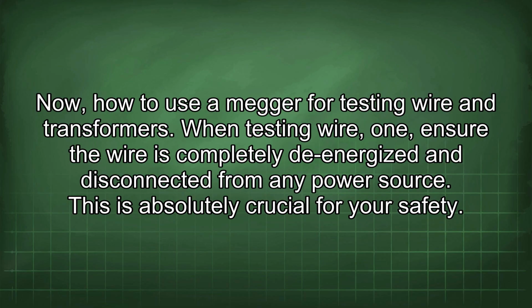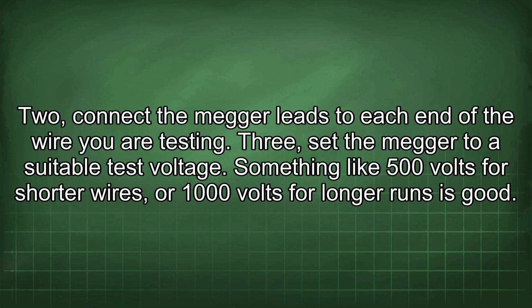When testing wire, 1. Ensure the wire is completely de-energized and disconnected from any power source. This is absolutely crucial for your safety. 2. Connect the Megger leads to each end of the wire you are testing. 3. Set the Megger to a suitable test voltage. Something like 500 volts for shorter wires, or 1000 volts for longer runs is good.